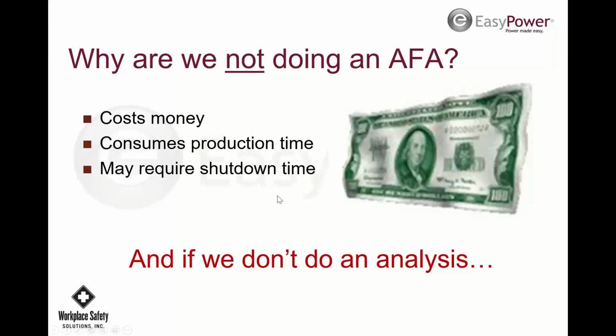It could consume productive time and may cause shutdown time. If we have a switchgear that we know, we do enough of a study to know what the fault current is, so we can go into the switchgear or not go into it. If we can't go into it because the fault current is too high or the clearing time is not low enough, then we have to schedule a shutdown with that company. And so usually that's a midnight on a Saturday night or some crazy thing. But they usually will do it for us if they want to get this study done.